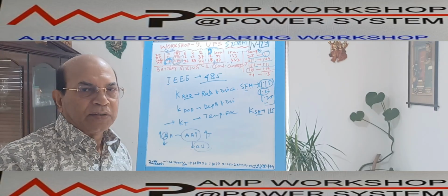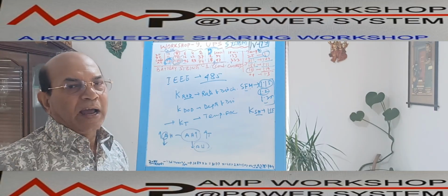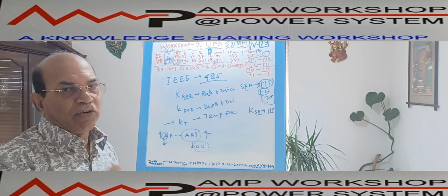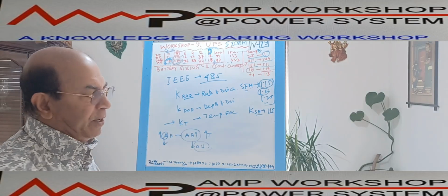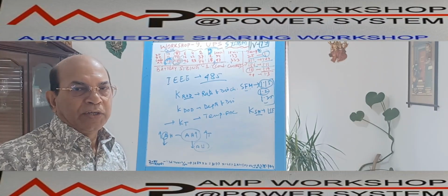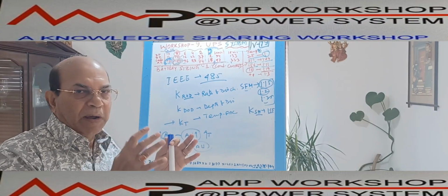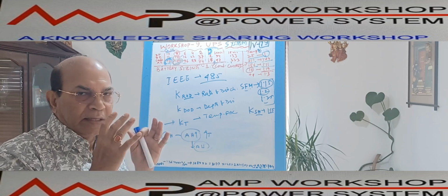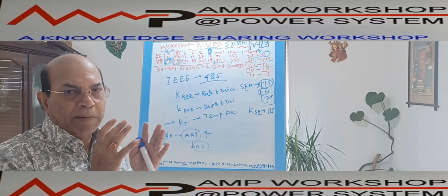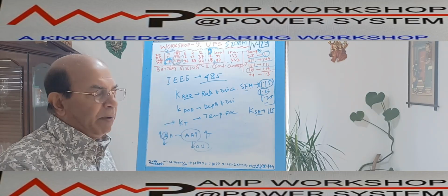If it is decreased, then to meet the requirement I have to put additional capacity inside. So a factor or margin is required due to the temperature. Most manufacturers specify their battery capacity when they are selling the battery. They say my battery has this amount of ampere hour capacity. They specify three parameters.